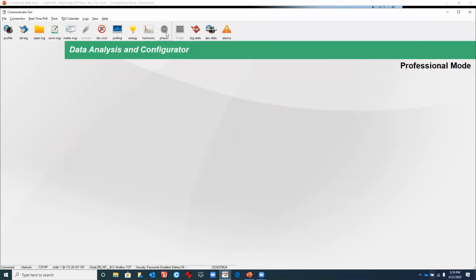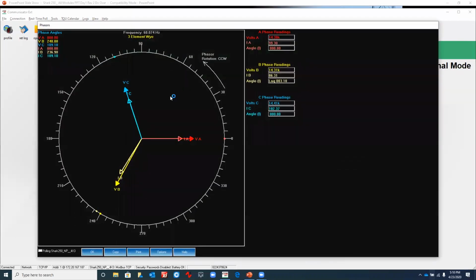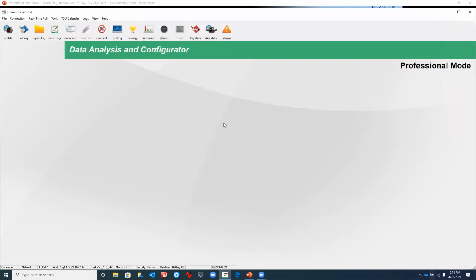Just a quick look, we'll discuss the phasor diagram real briefly. I know we'll talk about this tomorrow, but I think this is one of the most important screens to look at. It's a great tool to troubleshoot, verify wiring, and just gives people confidence that the wiring was installed properly. So this is an ABC rotation, A, B, and C, a 3-element Y. It shows you the amplitude, the magnitudes of the voltage, current, and the phase angle on all 3 phases. Total power would be the sum of all 3. So if we close that out.